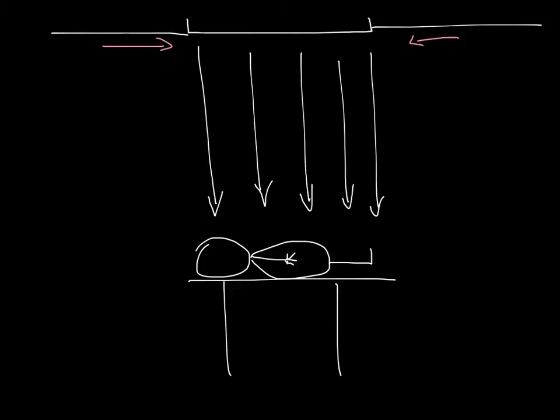Because of this, you often see air curtains around the perimeter of the operating room laminar diffusers. The air curtain is a perimeter of linear diffusers that surrounds the laminar flow diffusers that reduces the quantity of particles that enter the laminar flow field. It basically creates a barrier between the room air and the sterile field under the laminar flow diffusers.